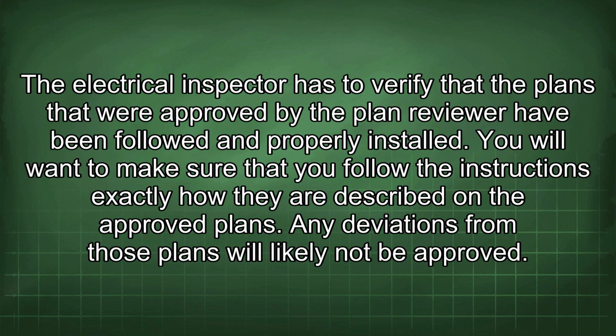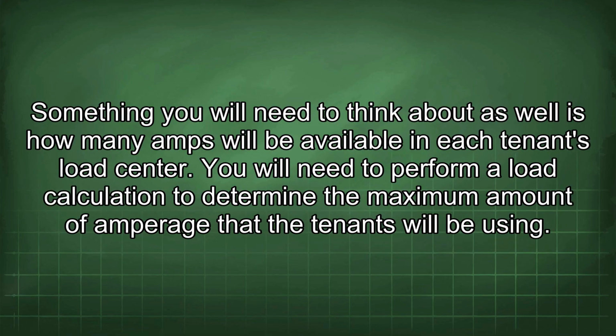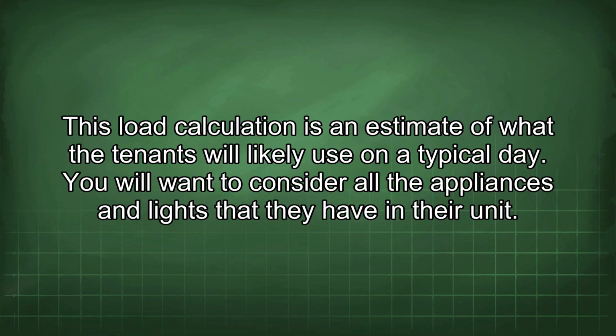The electrical inspector has to verify that the plans that were approved by the plan reviewer have been followed and properly installed. You will want to make sure that you follow the instructions exactly how they are described in the approved plans. Any deviations from those plans will likely not be approved. Something you will need to think about as well is how many amps will be available in each tenant's load center. You will need to perform a load calculation to determine the maximum amount of amperage that the tenants will be using. This load calculation is an estimate of what the tenants will likely use on a typical day.